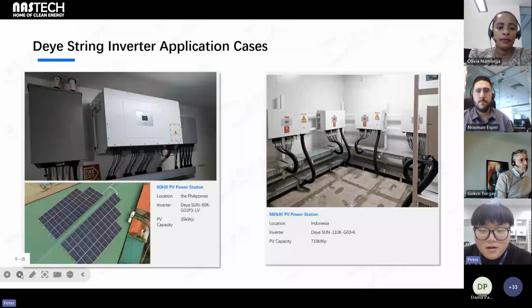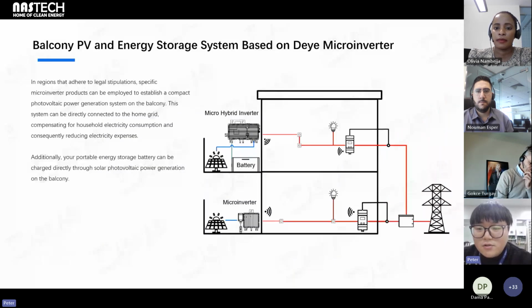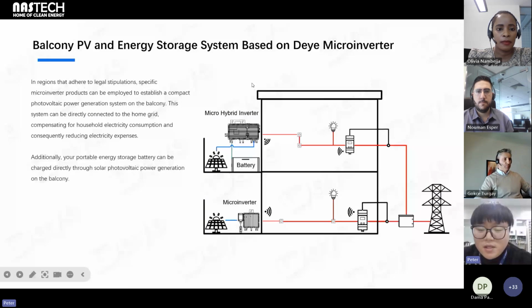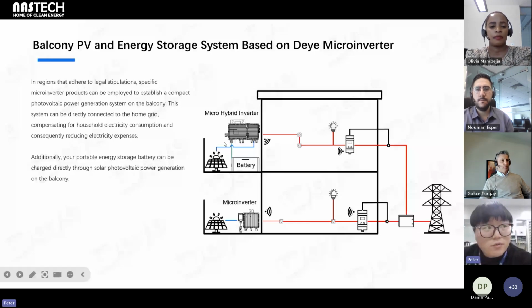And then there is the micro hybrid inverter solution. With the microinverter size and features, it can also connect a battery. You can run it like a small hybrid system. We can also use a wireless meter to do the zero export, because the microinverter will not have a meter connection for communication, as it needs to be IP67 waterproof and dustproof. So we use the wireless solution for the zero export.